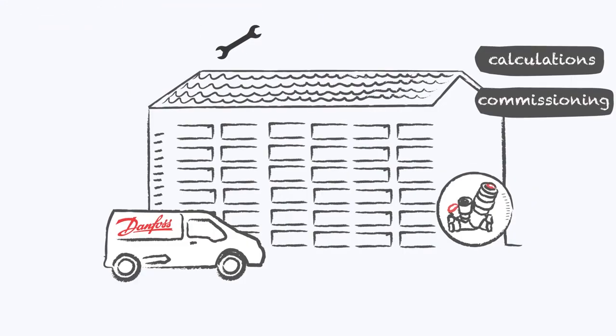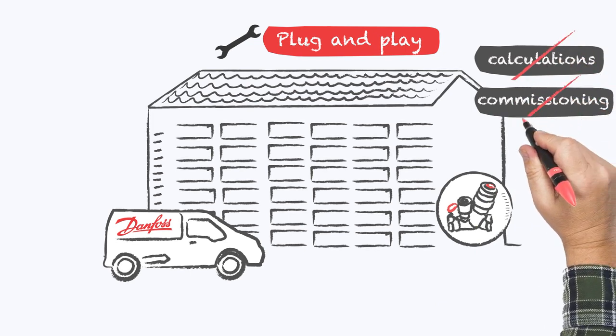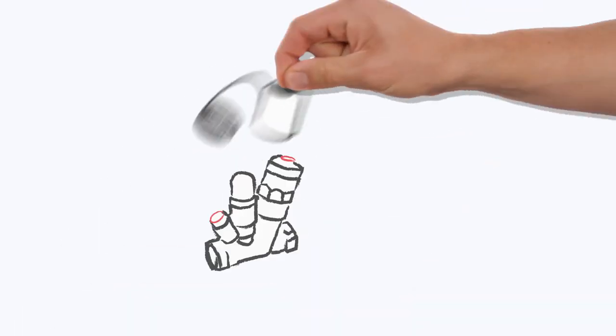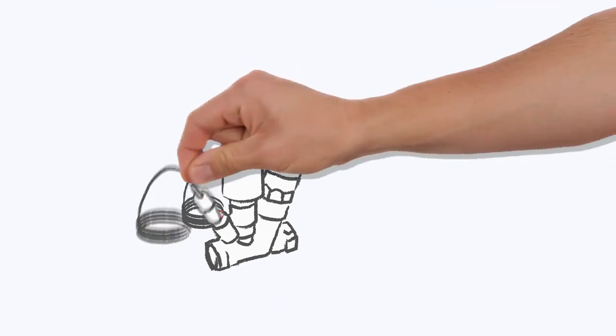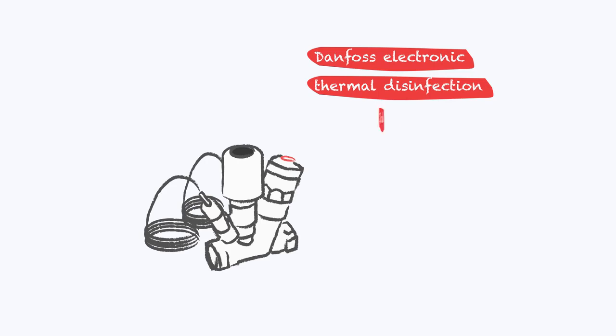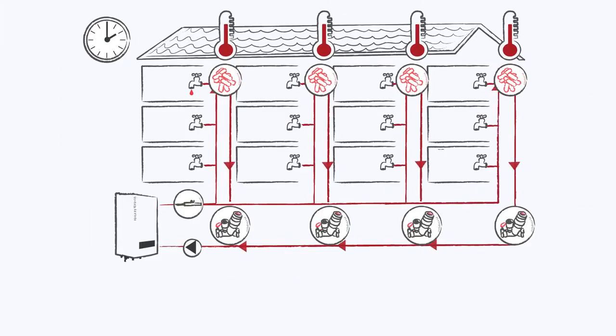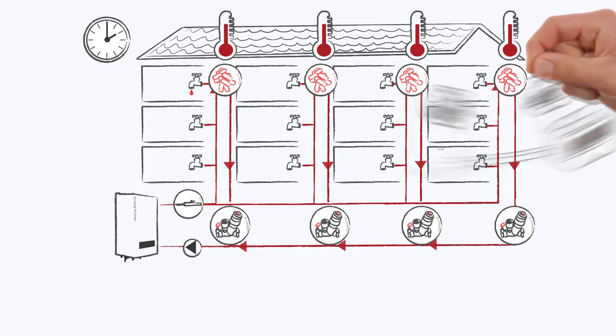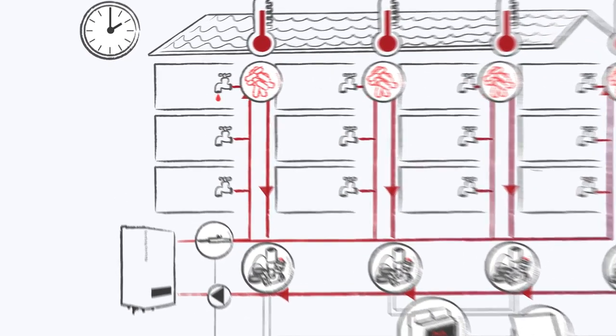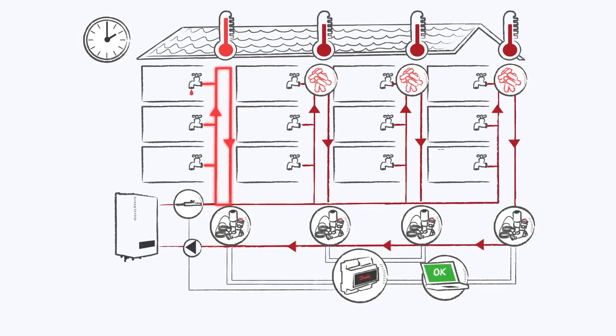And the installation itself is plug and play since flow calculations and commissioning are not required. Just as easy, the valves in the system can also be equipped with the advanced Danfoss electronic thermal disinfection CCR2 plus solution. This advanced electronic system guarantees efficient thermal disinfection by periodically flushing the system riser per riser at an extra high temperature to kill the Legionella bacteria.